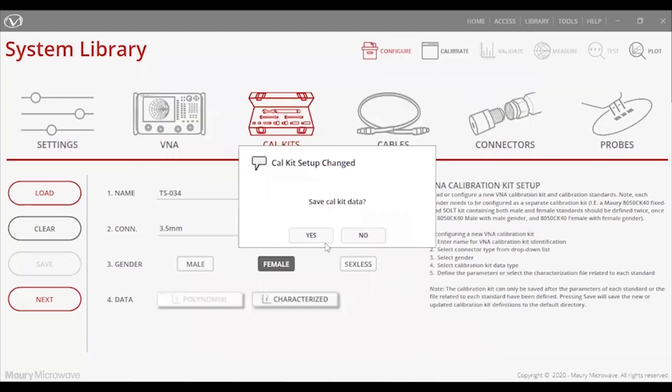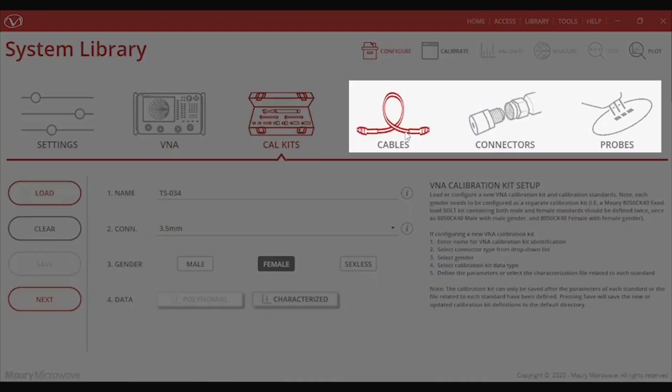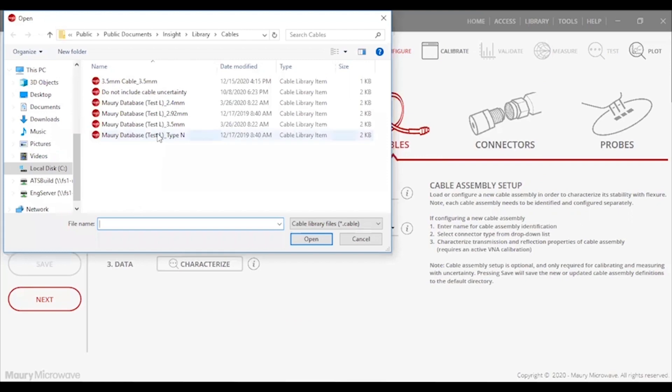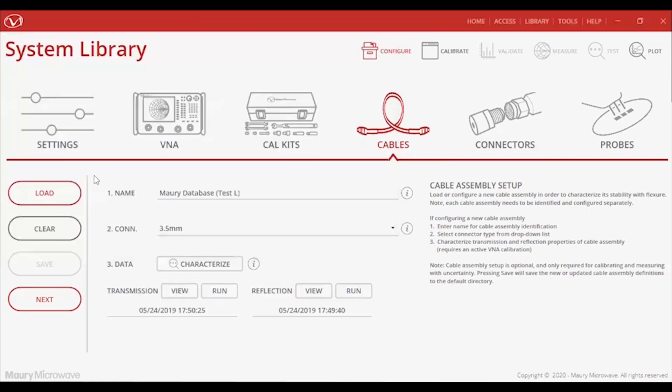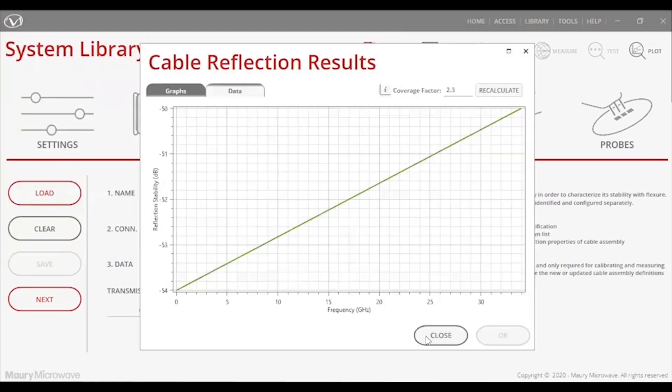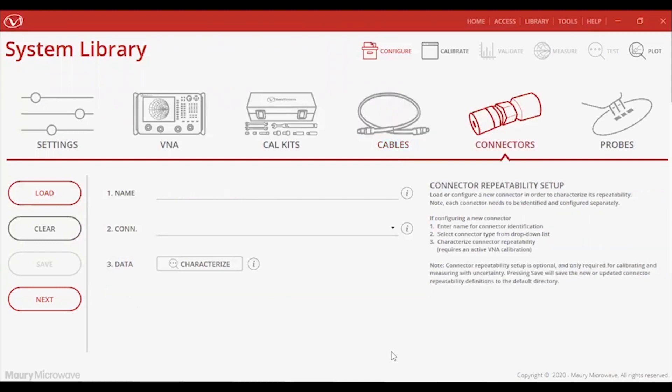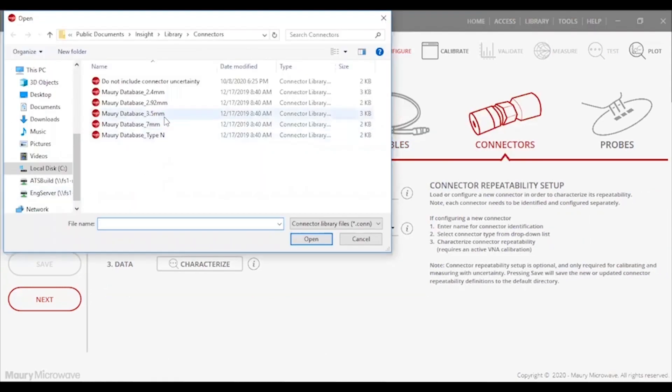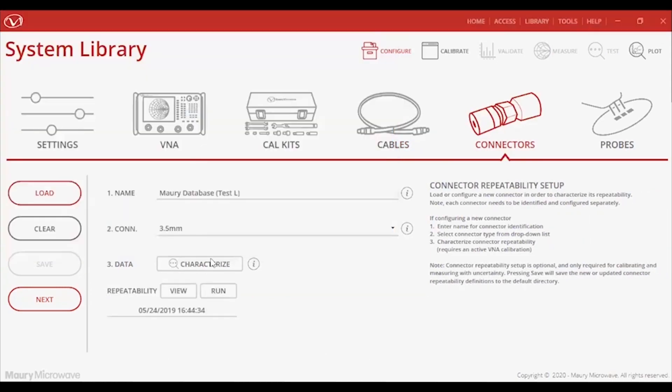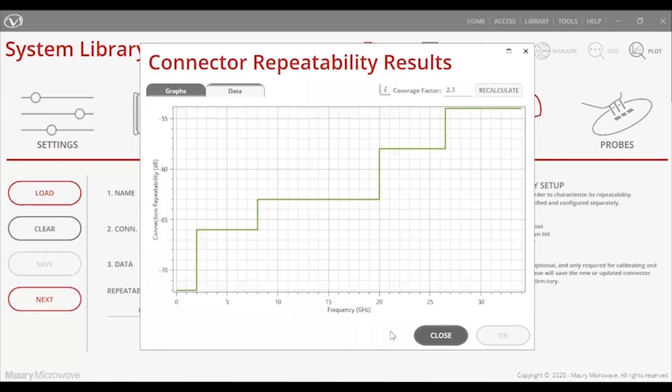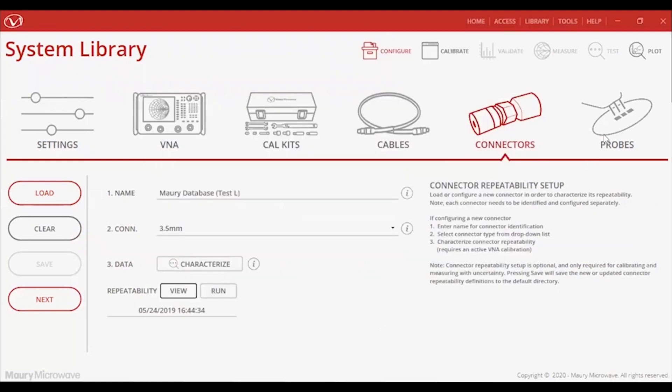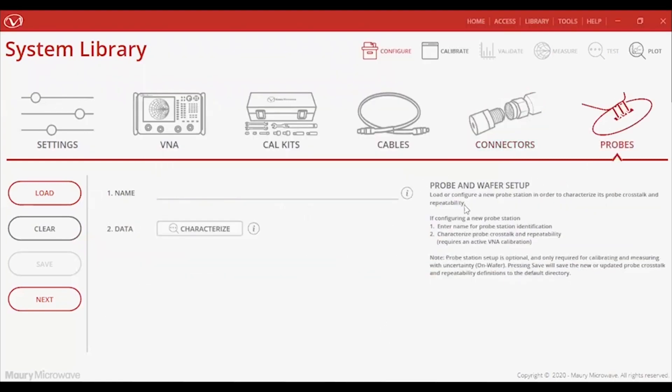You will notice three more tabs: cables, connectors, and probes. These are optional tabs to characterize the uncertainty contribution of flexing your specific cable, as well as connector and probe repeatability. When characterized and applied to the measurement, not only will you get S parameters, but you will get S parameters with uncertainty. We'll explore that more in a different video.